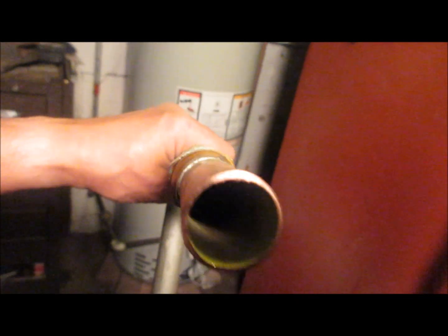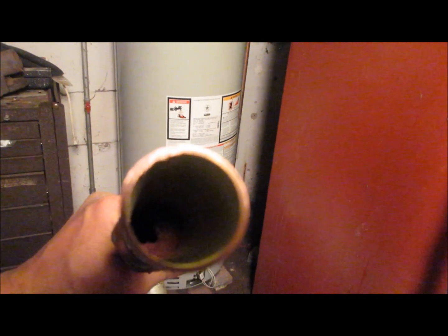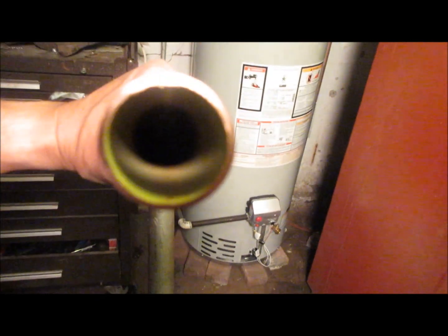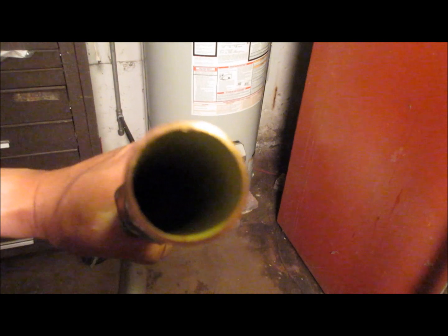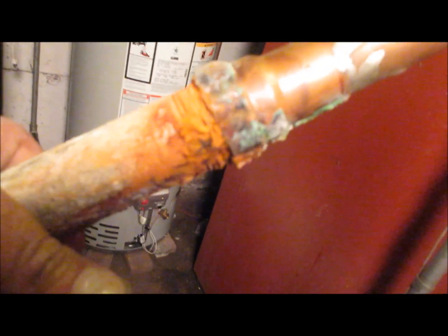This is 15 years ago — I knew I wasn't supposed to do this but I needed to change it out quick and used what was on hand. But if you think that's the bad part, that's not the bad part. Look right there — the pipe is halfway closed. We were only getting half the water pressure out of this, and it's even rusting on the inside.